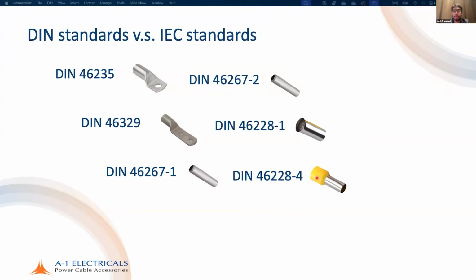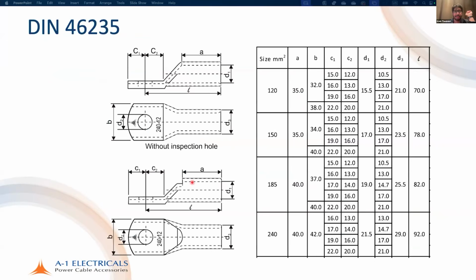Now you may be asking me, Krish, you are in IEC, you write the IEC standards. Why are you talking about DIN standards? The reason is IEC standards are written in a way so that they cover everything. So, for example, for the compression connectors, you have 61238-1-1 and -1-3. These are the test methods for these products. But the actual dimensions are specified in these DIN standards. Why is that important? Because it has to do with the crimping.